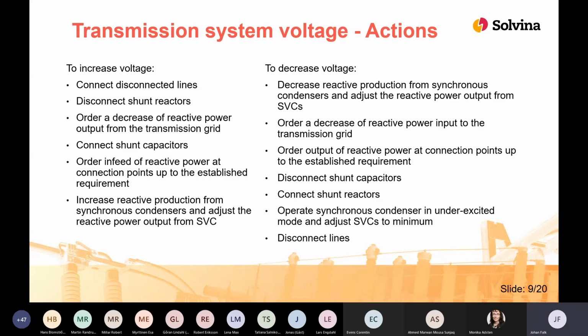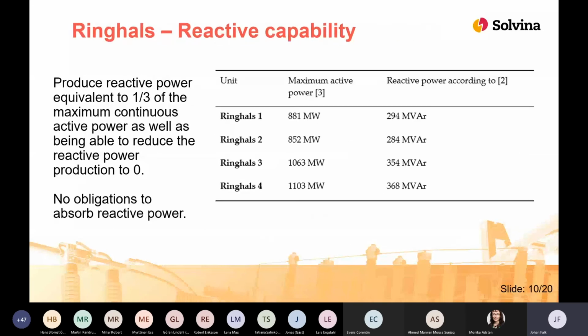So that was a bit about the transmission system side of this topic. Now we'll continue with a bit more focus on Ringhals. The time period, as I said, that we studied was up to 2019 in this historical grid data that we have been looking at, and this was before any decommissioning. And here we can see in this list the active and reactive power for each unit. The reactive power for each unit is what the unit is obligated to be able to produce, and this is according to the grid code.